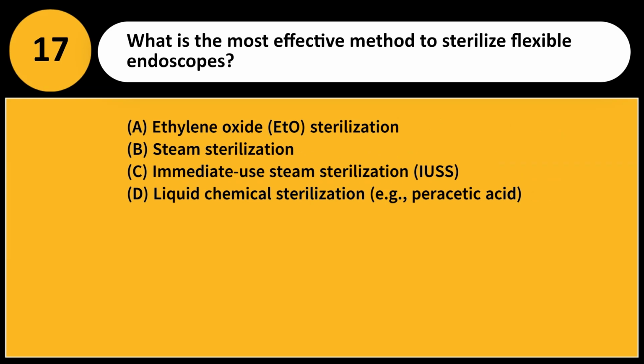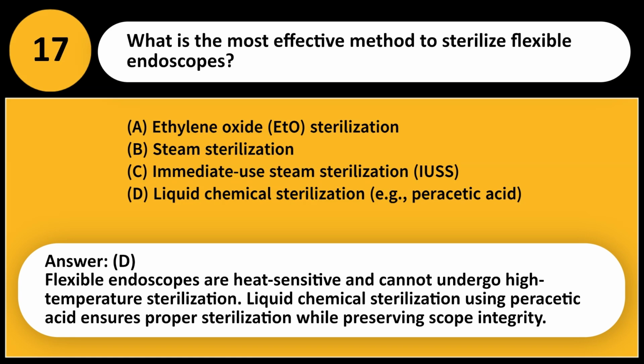What is the most effective method to sterilize flexible endoscopes? A. Ethylene oxide (ETO) sterilization. B. Steam sterilization. C. Immediate use steam sterilization (IUSS). D. Liquid chemical sterilization, e.g., peracetic acid. Answer D. Flexible endoscopes are heat-sensitive and cannot undergo high-temperature sterilization. Liquid chemical sterilization using peracetic acid ensures proper sterilization while preserving scope integrity.